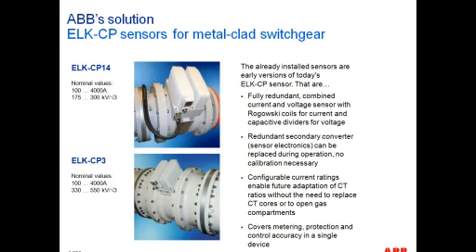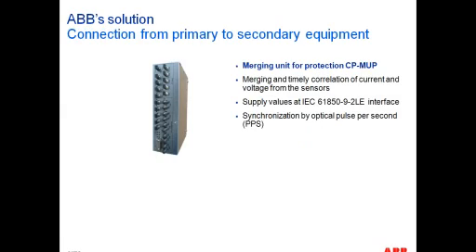In the case of this particular system, the merging unit interfaces with the CP14 and CP3 sensors, which are non-conventional instrument transformers, essentially based on Rogowski coil and capacitive dividers for voltage. These are non-conventional instrument transformers available in GIS, gas-insulated switchgear, that ABB offers. So from these non-conventional instrument transformers, they would interface with the merging unit, and then the merging unit would go ahead and publish the different voltage and current samples.